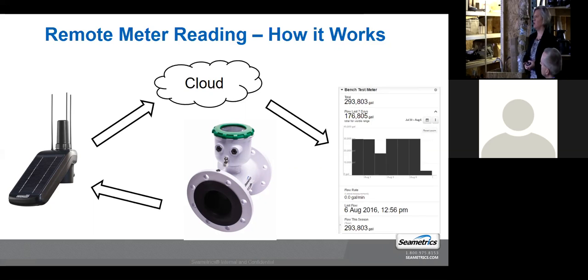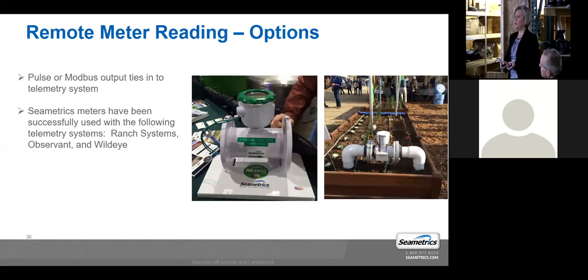I was at the World Ag Expo show in Tulare last week, and there are dozens and dozens of telemetry companies that are doing this. We've been working closely with a number of them to ensure that our meters are compatible with a number of systems. At this time, we don't offer a telemetry system per se, but the pulse output, or let's say the Modbus output, we're seeing Modbus is becoming a cleaner communication protocol. Whatever that meter is reading at that given time, Modbus will give that direct communication across the cloud, and that's the data that you're going to get. There's no lapse in time like there is with pulse output.